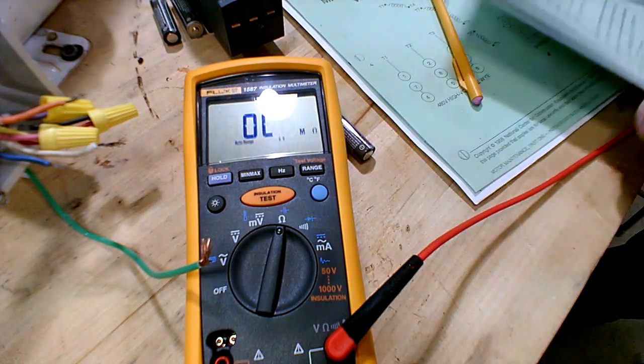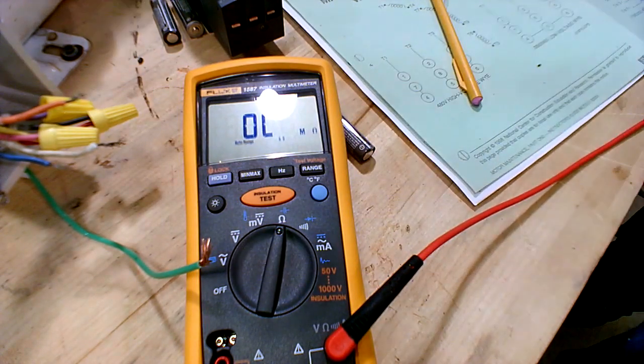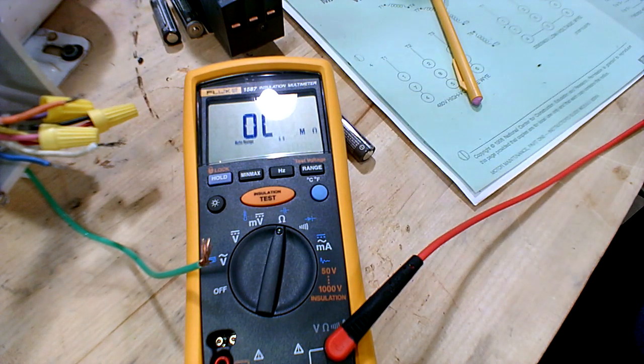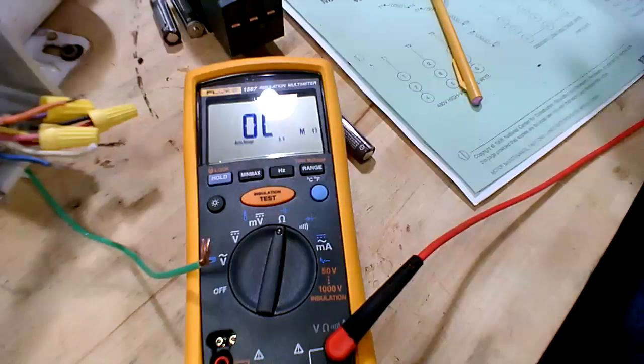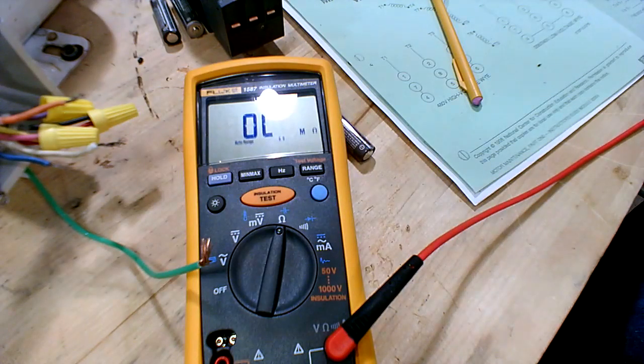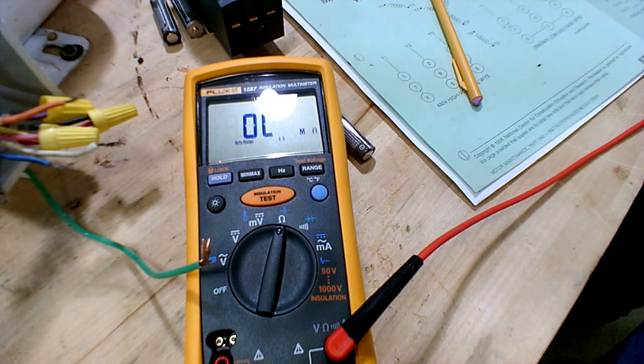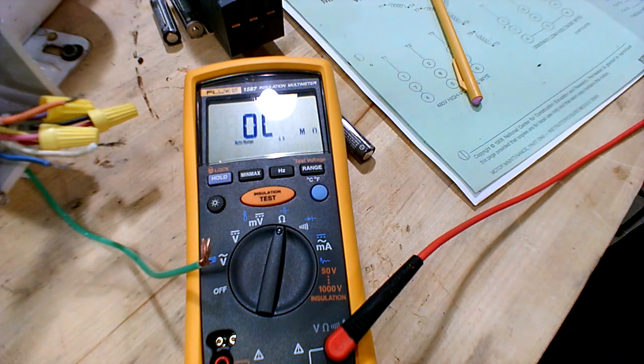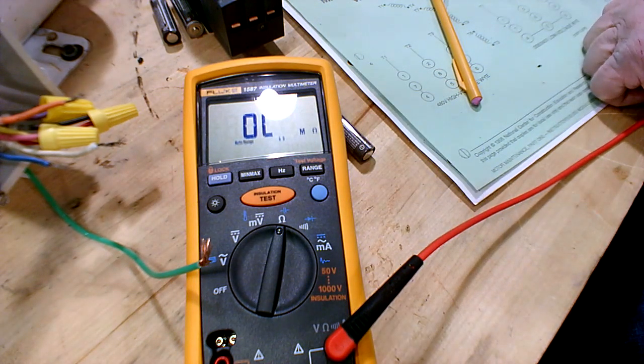Get your name on there. That's going to be a 100. Keep that. And look, the same test can be done on a Delta as well. But when you do it, it goes to high voltage. You put the highest voltage on there from that meter, shoot on the highest range, and you get that test. You keep these. Remind me to show you a Delta motor back in this cabinet for Tuesday, and then you can actually see the Delta.